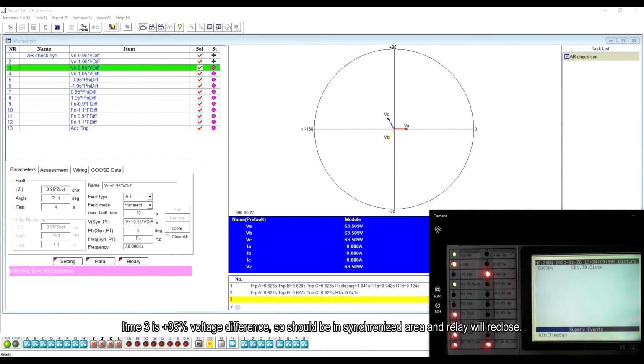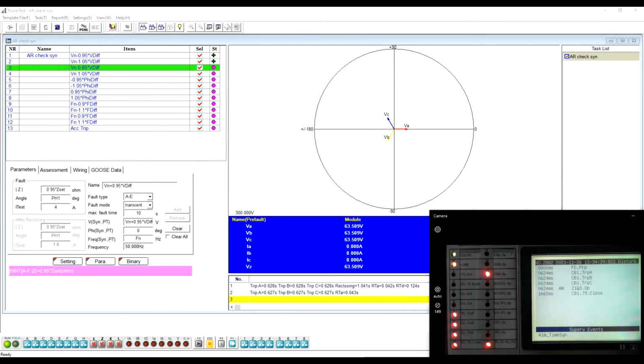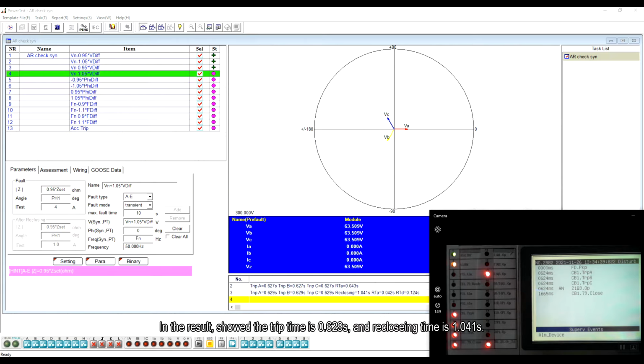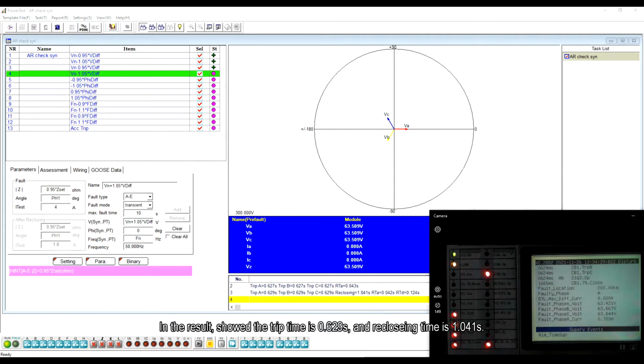Item 3 is positive 95% voltage difference, so should be in synchronized area and the relay will reclose. In the result, shown the trip time is 0.629 seconds and the reclosing time is 1.041 seconds.